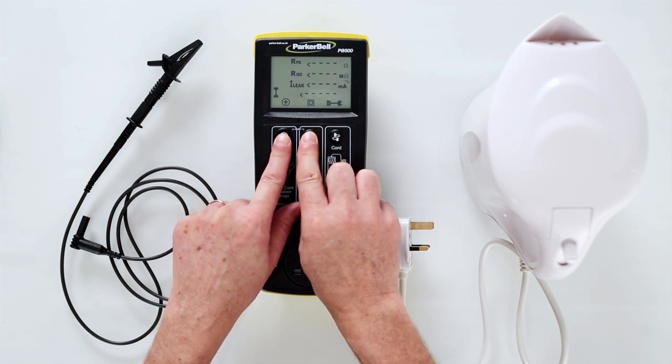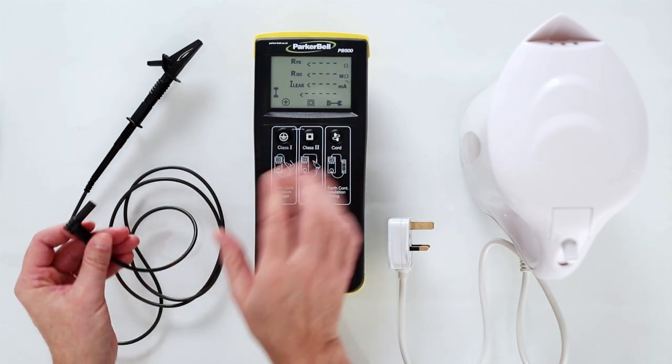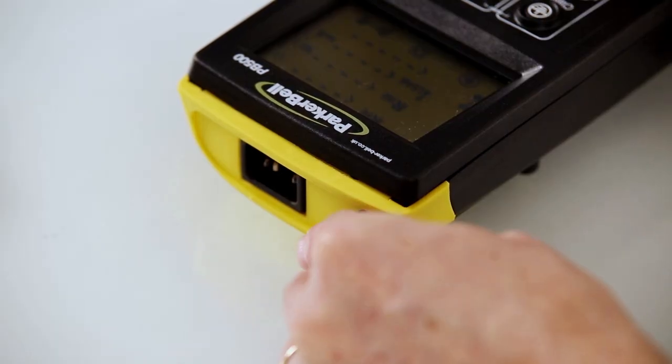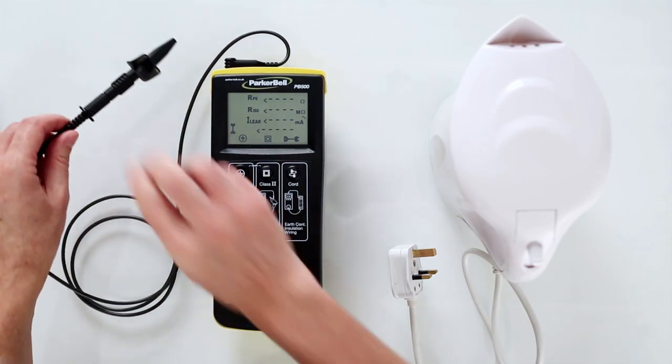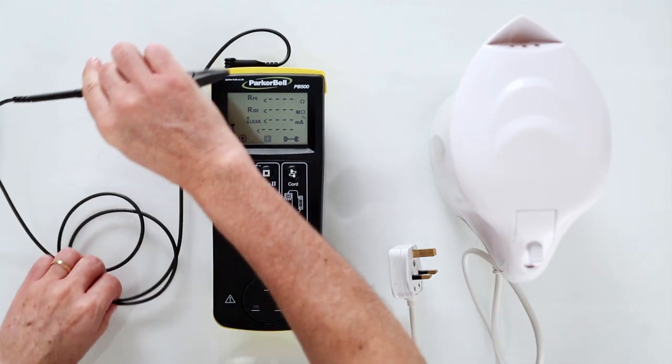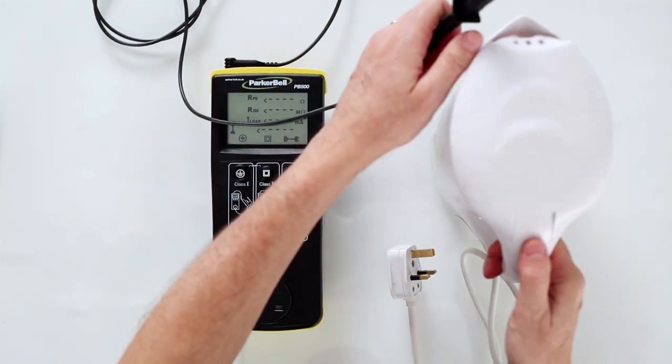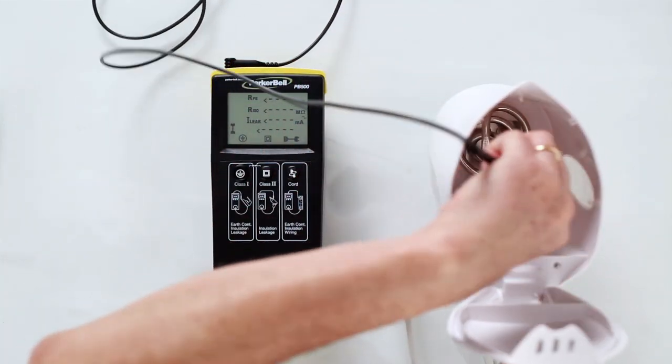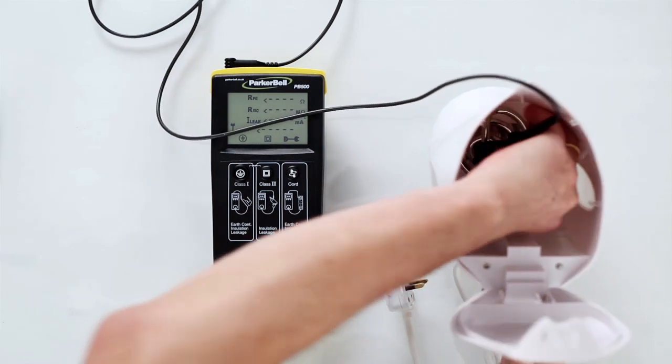Insert the round jack of the earth test lead into the top of the PB500 and using either the probe or the crocodile clip, connect it to an external earth point on the appliance. This will be a metal part.